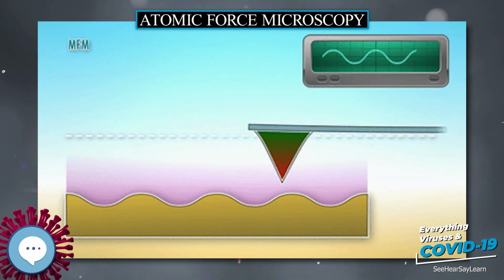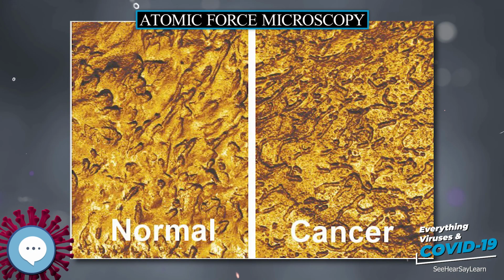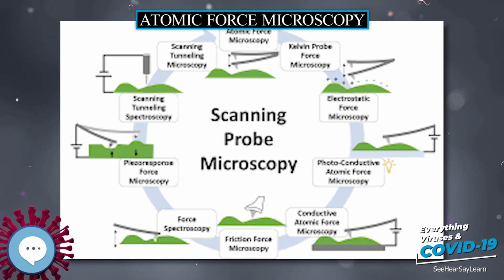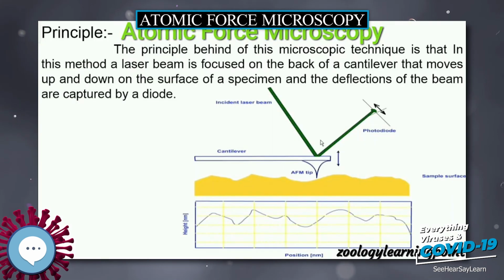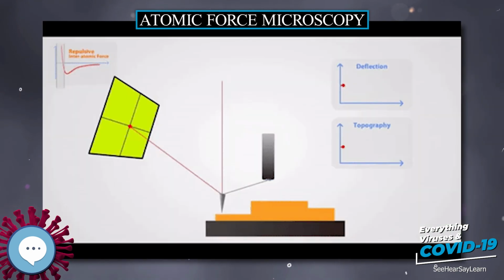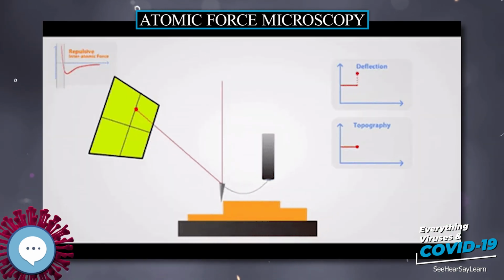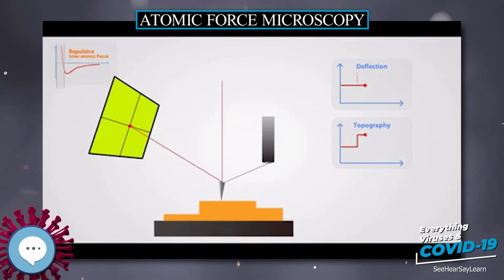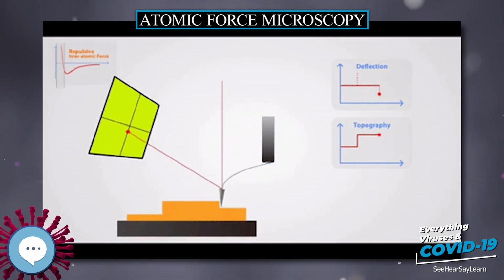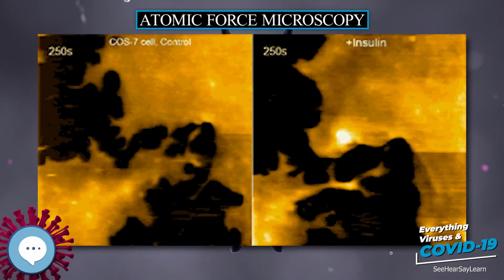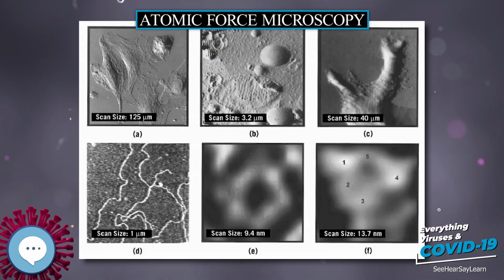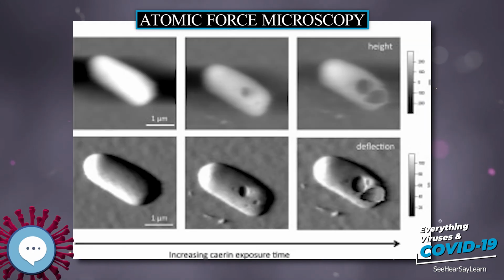AFM cantilever deflection measurement. Beam deflection measurement. The most common method for cantilever deflection measurements is the beam deflection method. In this method, laser light from a solid-state diode is reflected off the back of the cantilever and collected by a position-sensitive detector, PSD, consisting of two closely spaced photodiodes, whose output signal is collected by a differential amplifier. Angular displacement of the cantilever results in one photodiode collecting more light than the other photodiode, producing an output signal, the difference between the photodiode signals normalized by their sum, which is proportional to the deflection of the cantilever.